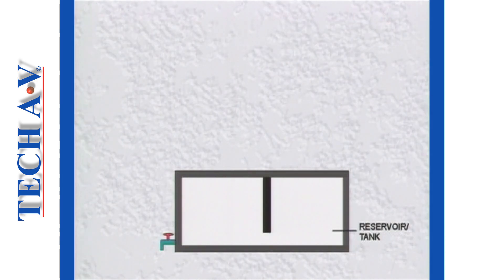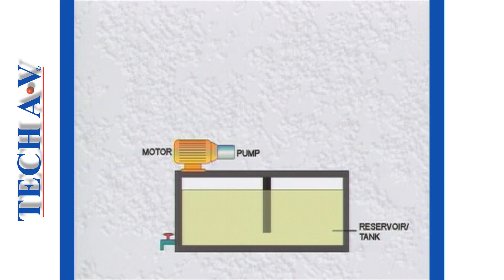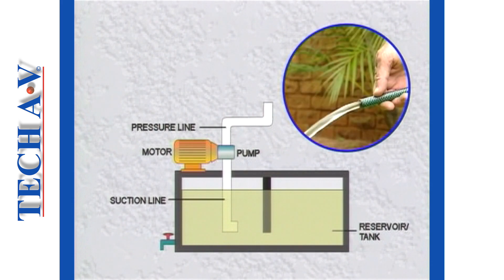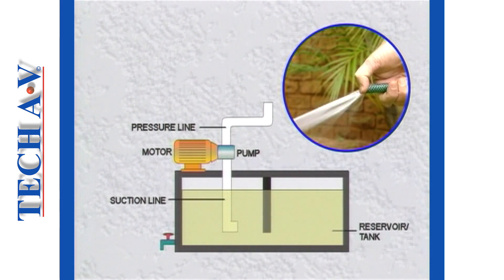A power pack usually comprises a reservoir or tank that contains the oil for the system, and the hydraulic pump and its drive motor. The purpose of a pump is to provide the required flow of oil within a system. Oil is drawn to the pump from the tank through a suction line; the pump then discharges the oil through its outlet into the pressure line. As we learned earlier, flow on its own does not result in pressure until that flow meets a restriction.